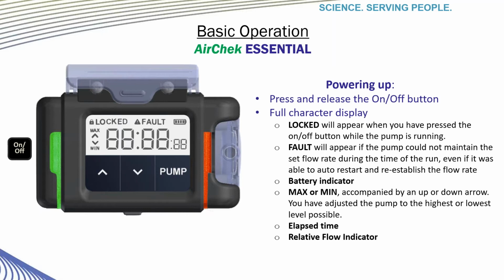The part of the clock that displays seconds, which is the 2 smallest characters of the clock, are also used in a certain screen to display what we call relative flow. This is a number between 1 and 99 that changes as you adjust the flow. It will be a little different for each pump as far as that number and as it relates to the flow rate, but this is intended just to give you a rough indication of the flow rate. In some ways similar to the old ball float that we used to use on some of the older pumps.